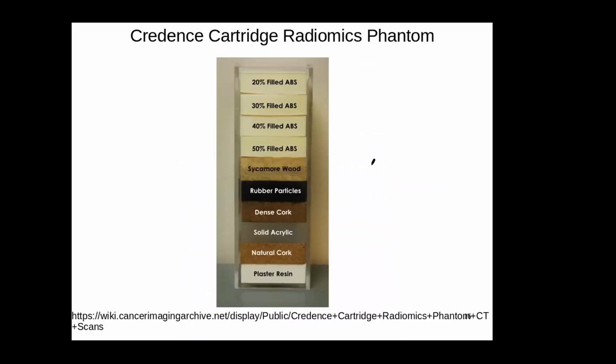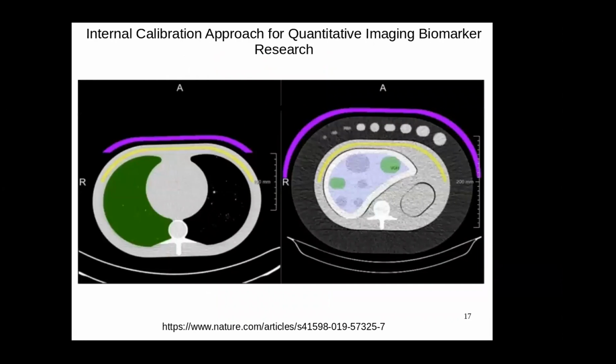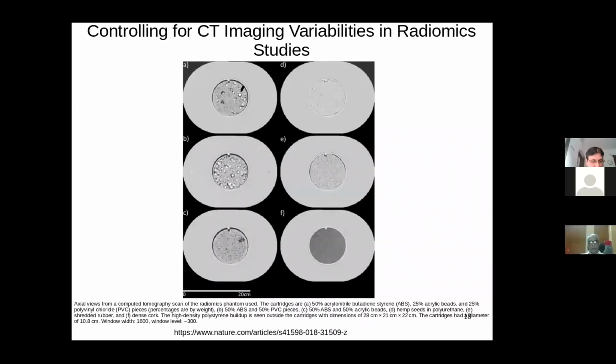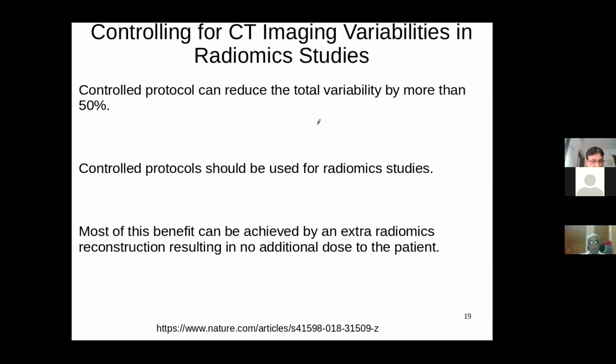There is another phantom we can use, the Credence Cartridge radiomics phantom. Then there are some methods researchers have suggested. You can use the patient image itself as a calibration. You can draw a background region here, and maybe another one here, or actually one background is enough, depending on which organ you are working on. You use that as a self calibration, also called an internal calibration. This is also quite useful. And there are some phantoms available, or we can design phantoms with multiple features or multiple materials, and use them to analyze how the features vary.